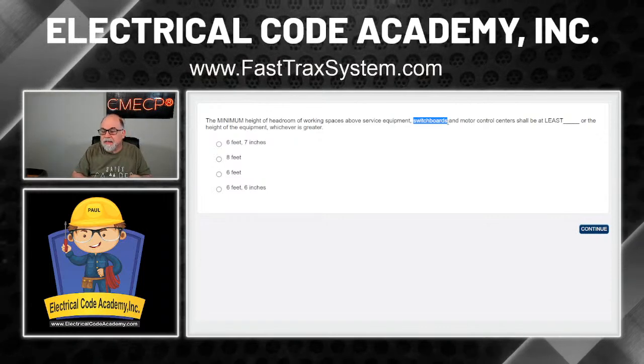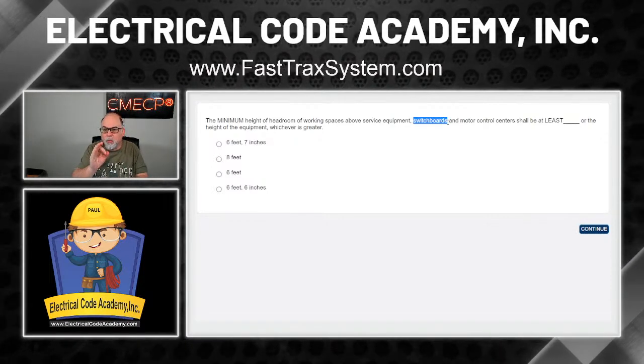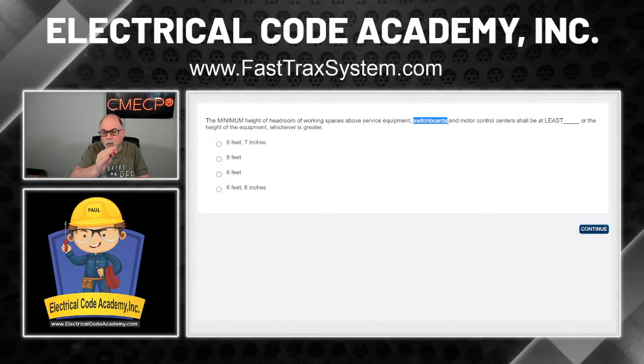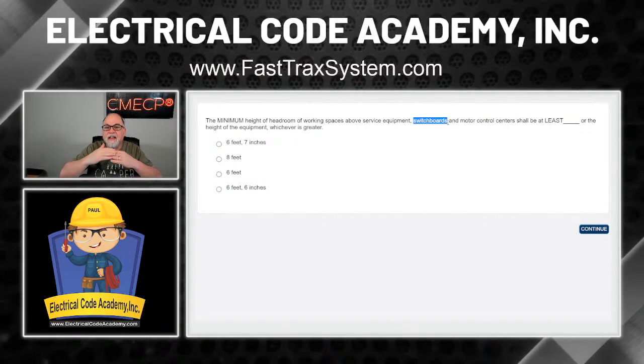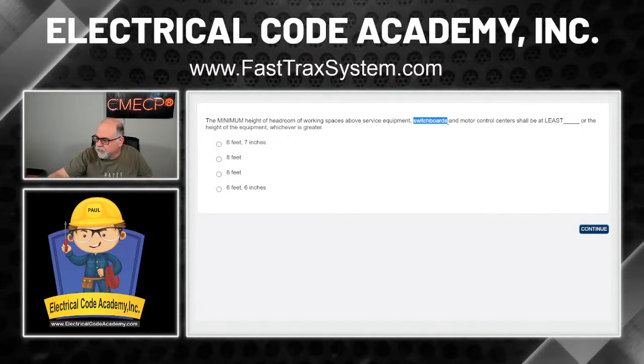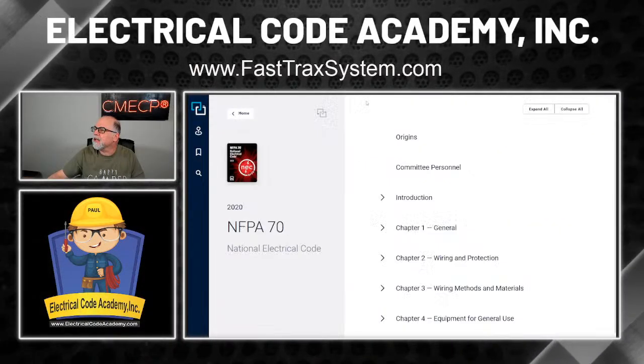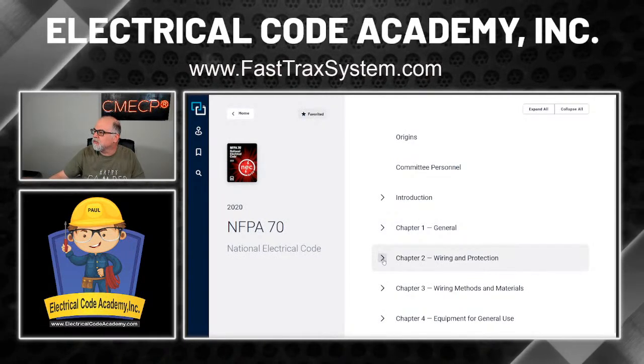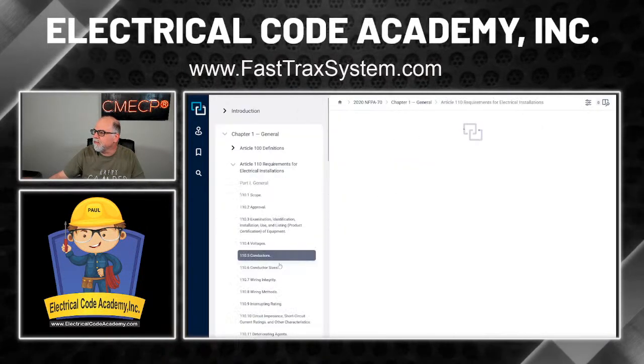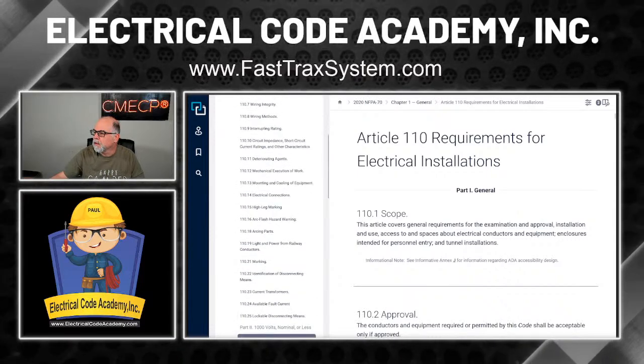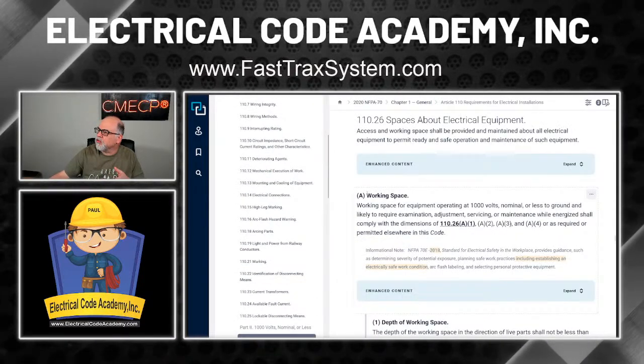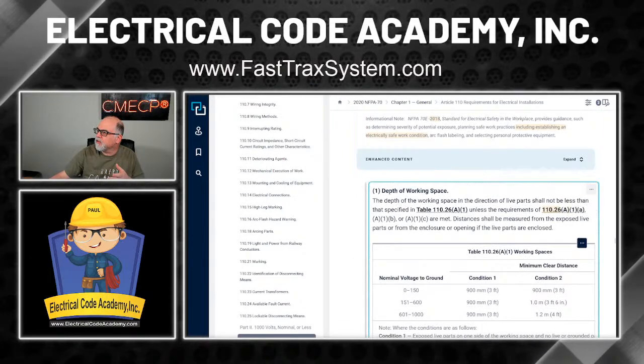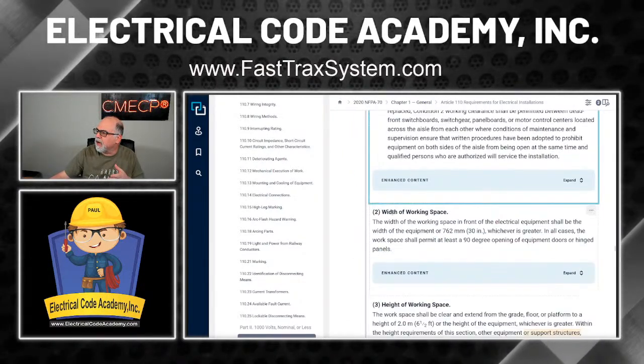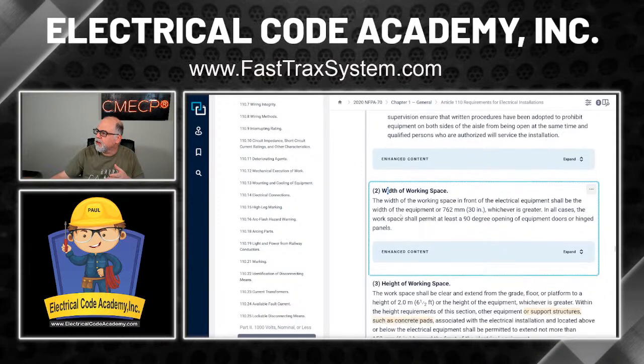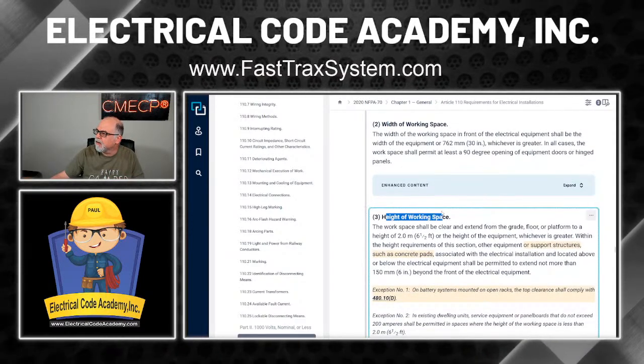All right. So with that said, we're going to go to 110.26 and we're looking for what? The headroom of the working space. Not the working space, the headroom. Okay. So let's go look at it. Let's go to the code. And I'll get us back to the beginning here. And let's go to 110.26 like it said. Right here. All right, so here's your working space, and here's the depth of the working space. Here's the height of the working space. The width of it, and here's your height right here.